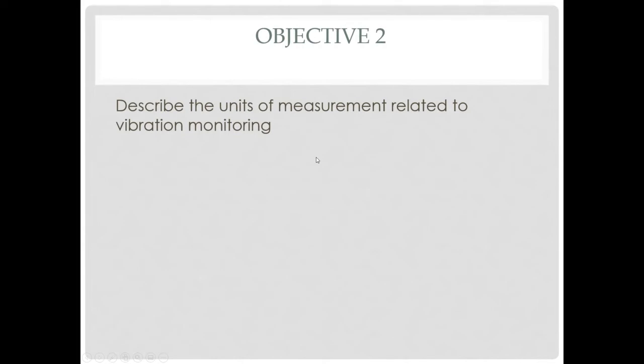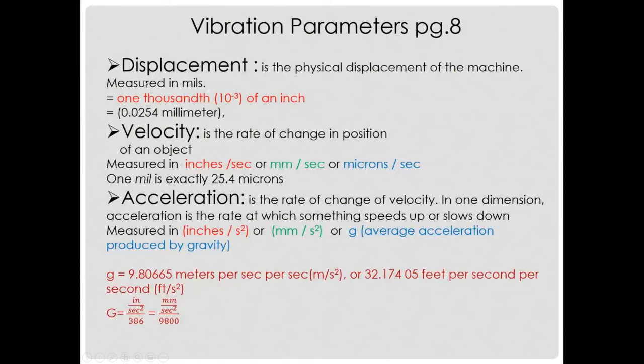Moving into objective two: describing the units of measurements related to vibration monitoring. Displacement — the physical displacement of the machine — here in Canada is usually still measured in mils, though we can also do it in millimeters. Velocity, the rate of change, is measured in inches per second. Acceleration is inches per second squared. So the typical units are thousandths of an inch, inches per second for velocity, inches per second squared for acceleration, and then our good old friend gravity at 9.81.